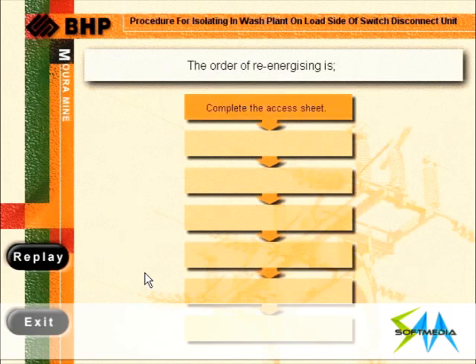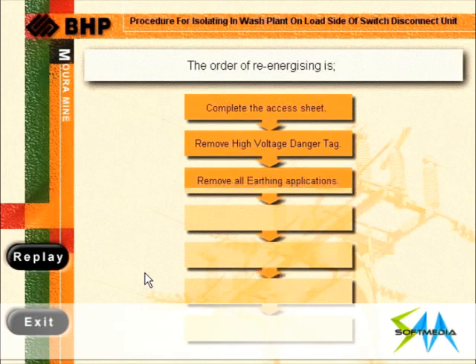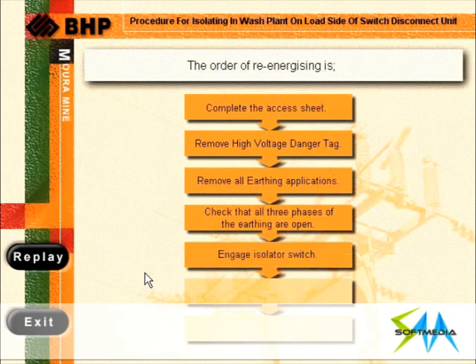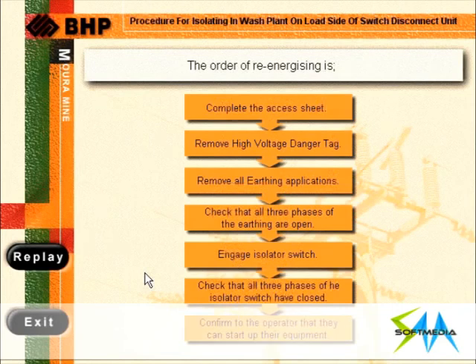That's the wrong choice. The correct order must be followed to re-energize the high voltage circuit. The order of re-energizing is: complete the access sheet, remove high voltage danger tag, remove all earthing applications, check that all 3 phases of the earthing are open, engage isolator switch, check that all 3 phases of the isolator switch have closed. Confirm to the operator that they can start up their equipment.